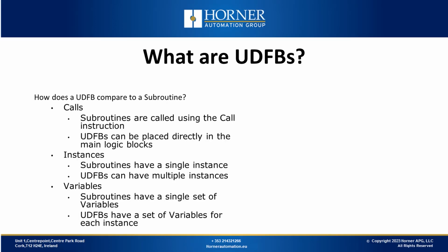So how does a UDFB compare to a subroutine? Subroutines are called using the call instruction, and you can use multiple call instructions in your code. However, no matter how many times you call a subroutine, it's the same code with the same variables. On the other hand, user-defined function blocks can be placed directly in the main logic blocks throughout your program, offering multiple instances.